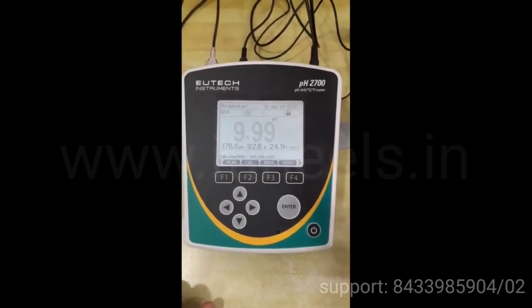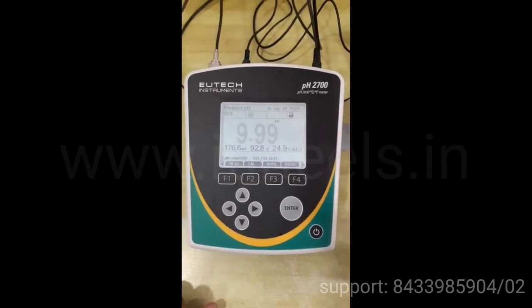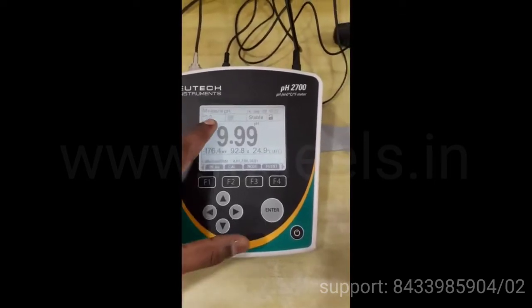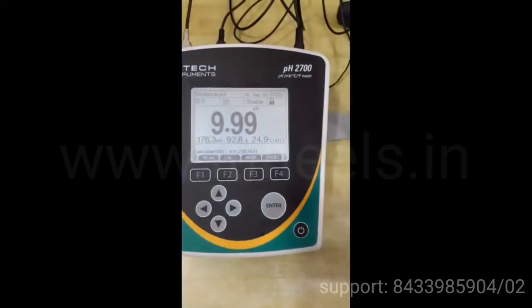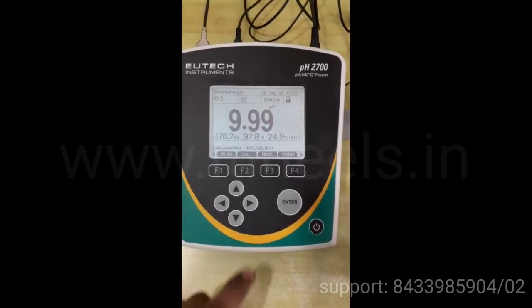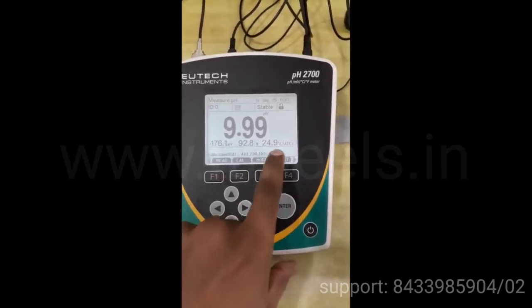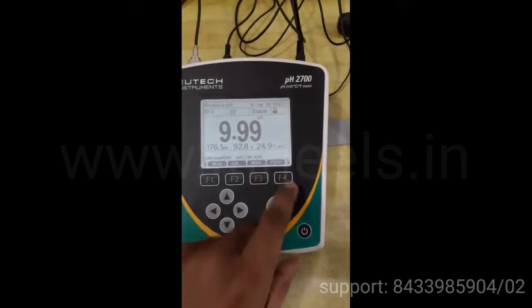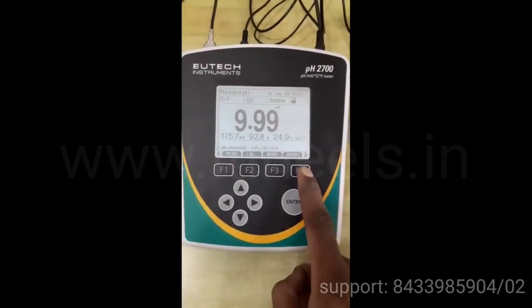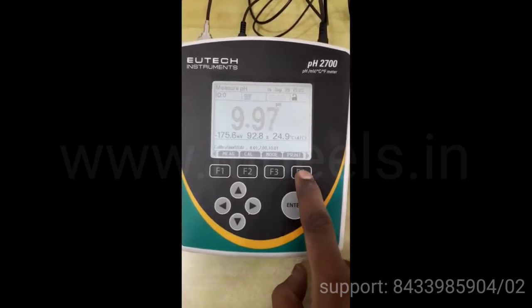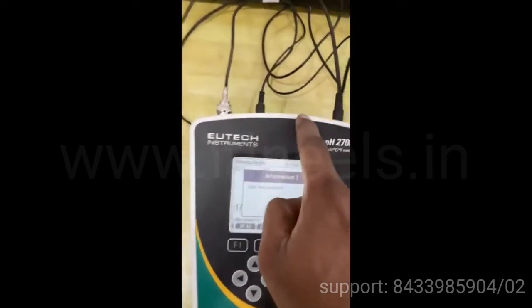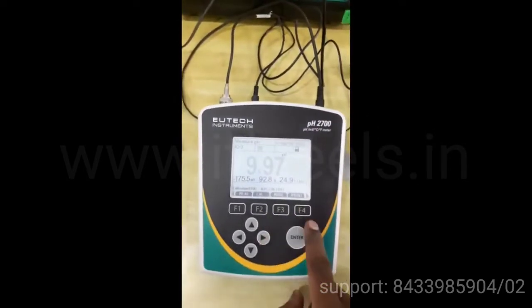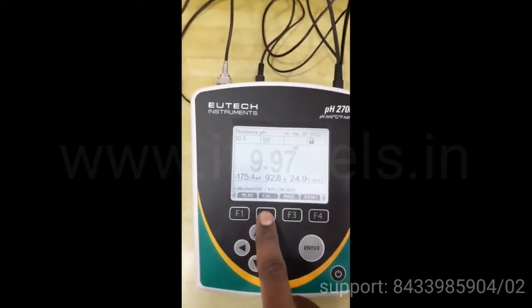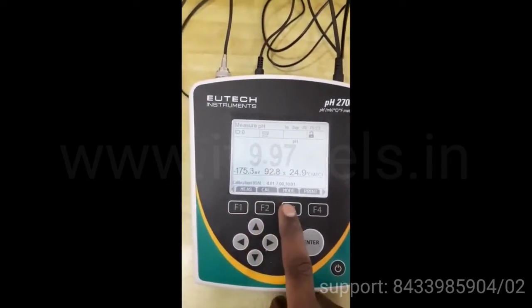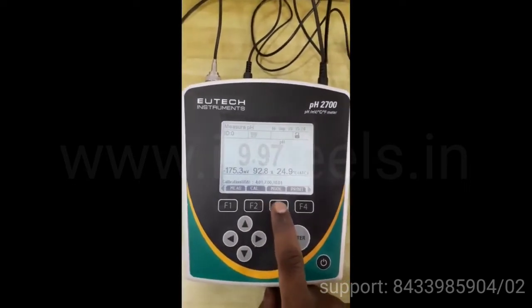Now you have to wait for a stable reading. In measurement mode also you will get the stable indication. Right now we are dipped in 10 and we are getting 9.99. The slope is also displayed, millivolt is also displayed, as well as the temperature of the sample. You can take a printout of this reading also by pressing print and attaching an RS-232 cable at the back and connecting to the printer. So this button is for entering the calibration mode.